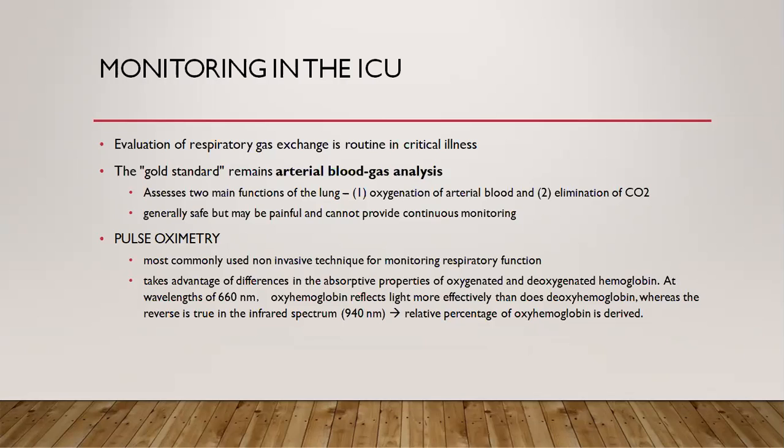Hence, what is commonly used is pulse oximetry. It is most commonly used as a non-invasive technique for monitoring respiratory function. It takes advantage of differences in the absorptive properties of oxygenated and deoxygenated hemoglobin. So at wavelengths of 660 nanometers, oxyhemoglobin reflects light more effectively than does deoxyhemoglobin.